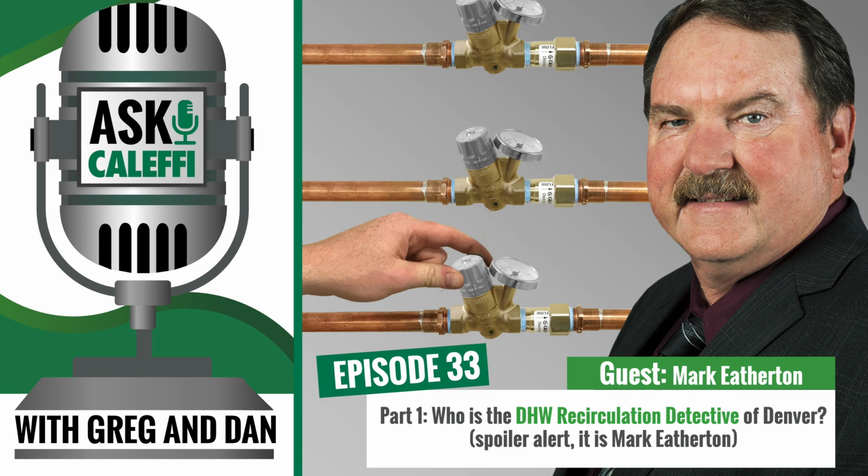Right. And basically you start seeing little pinhole leaks a couple of inches after elbows. Then we know it's hydraulic erosion. We cut the pipe apart, we split it in half, and you see a V-shaped track. And you remember that horses always walk upstream, so you know what direction the water was flowing through there.